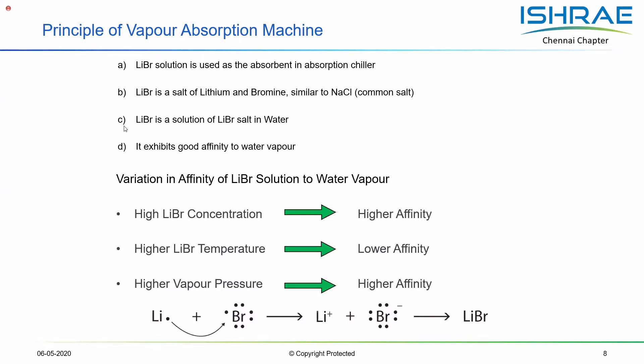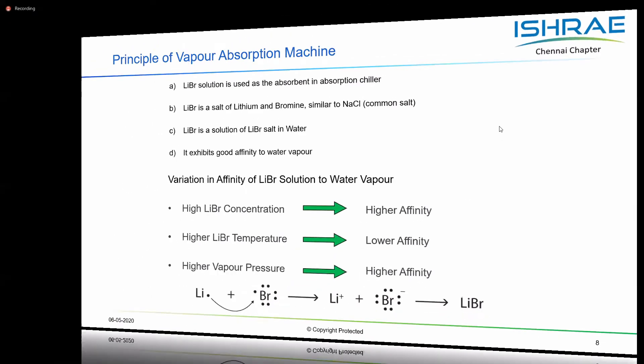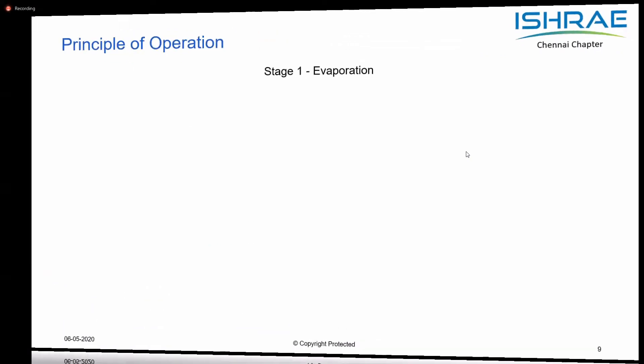This particular solution — salt and water — is the one which does the compression activity. The reason for using a salt solution in this system is that it has a very good affinity towards water, meaning that it is deliquescent by nature; it can absorb moisture. This particular property is used in the system, and the affinity towards water vapor improves as the concentration of the solution increases and is very good when the temperature is low.